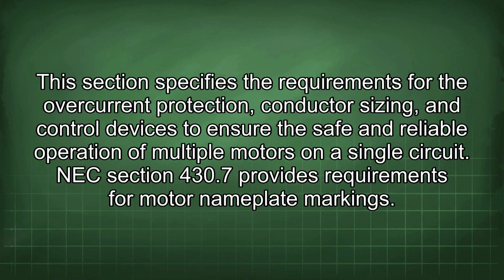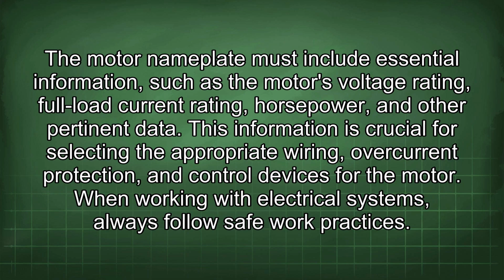NEC Section 430.7 provides requirements for motor nameplate markings. The motor nameplate must include essential information such as the motor's voltage rating, full load current rating, horsepower, and other pertinent data. This information is crucial for selecting the appropriate wiring, overcurrent protection, and control devices for the motor.